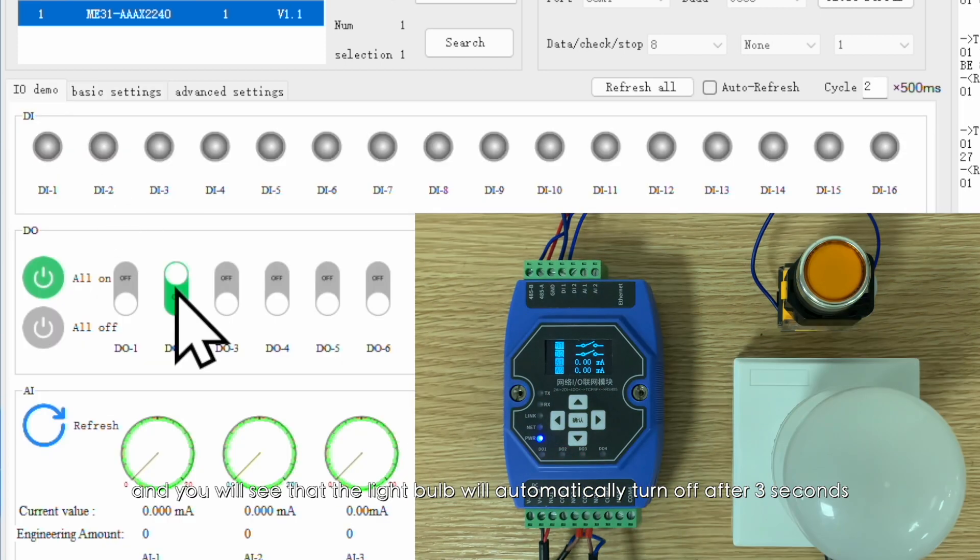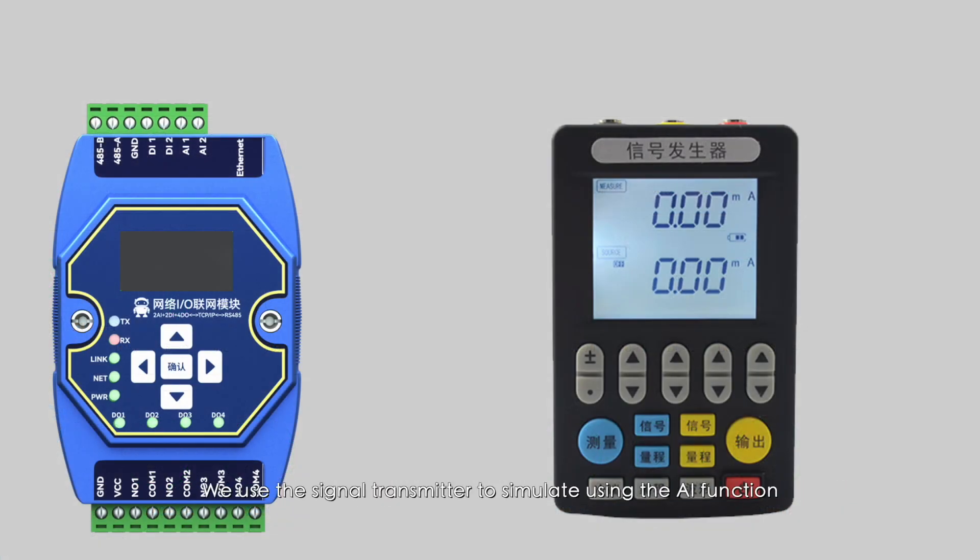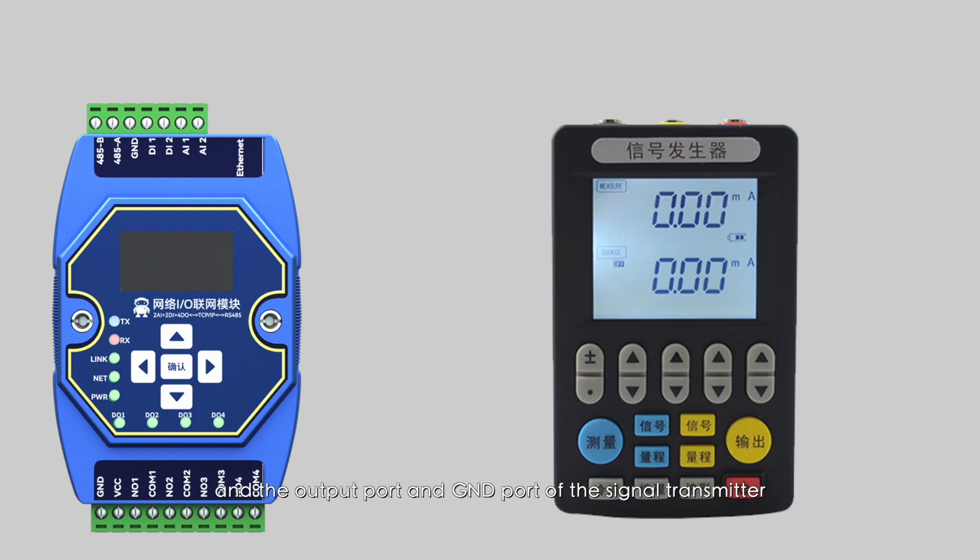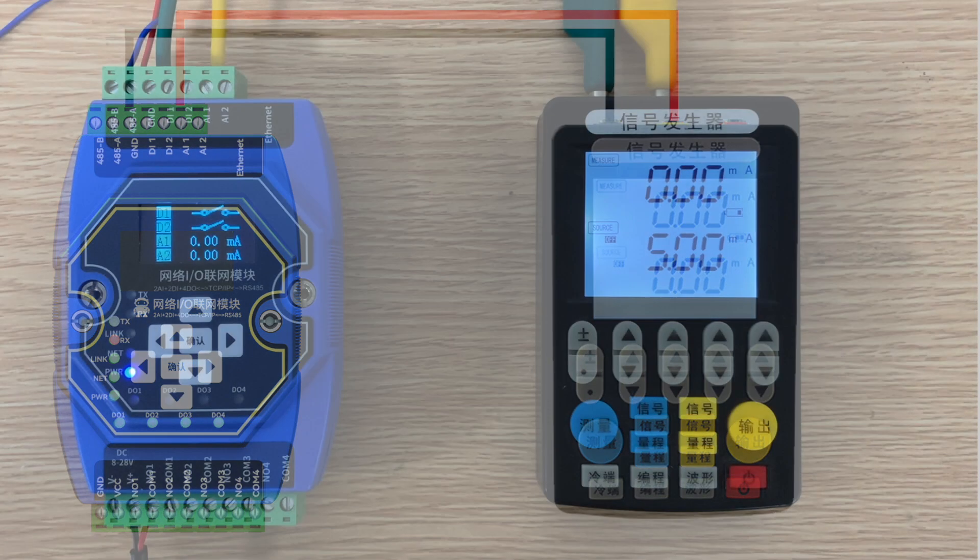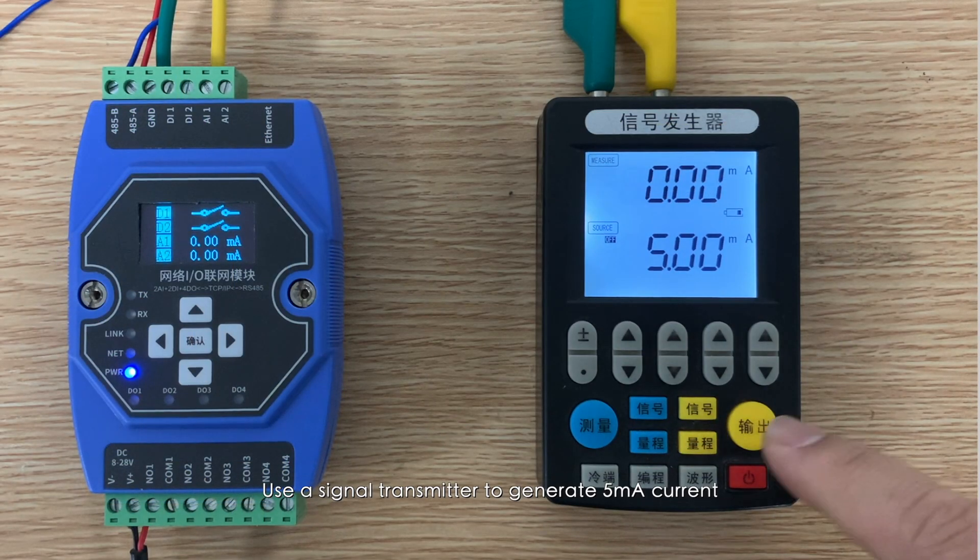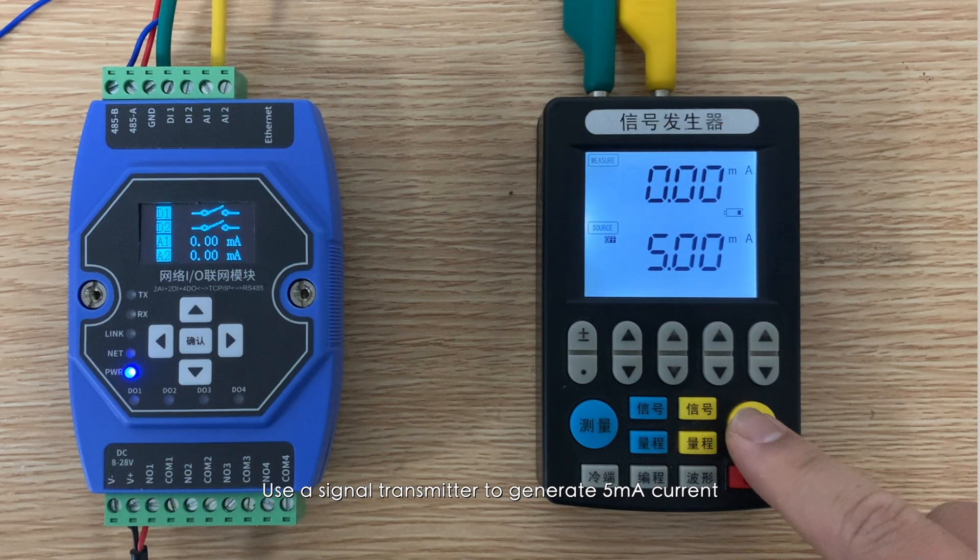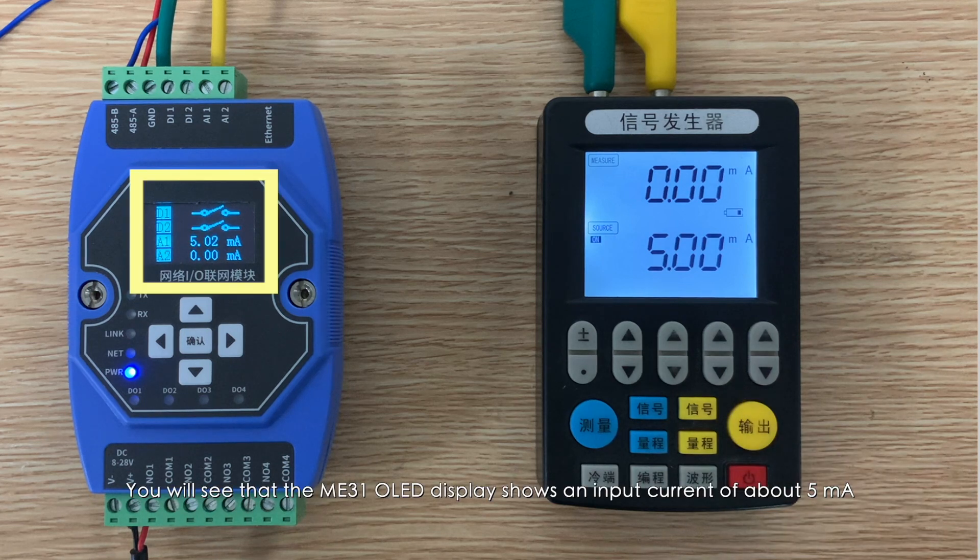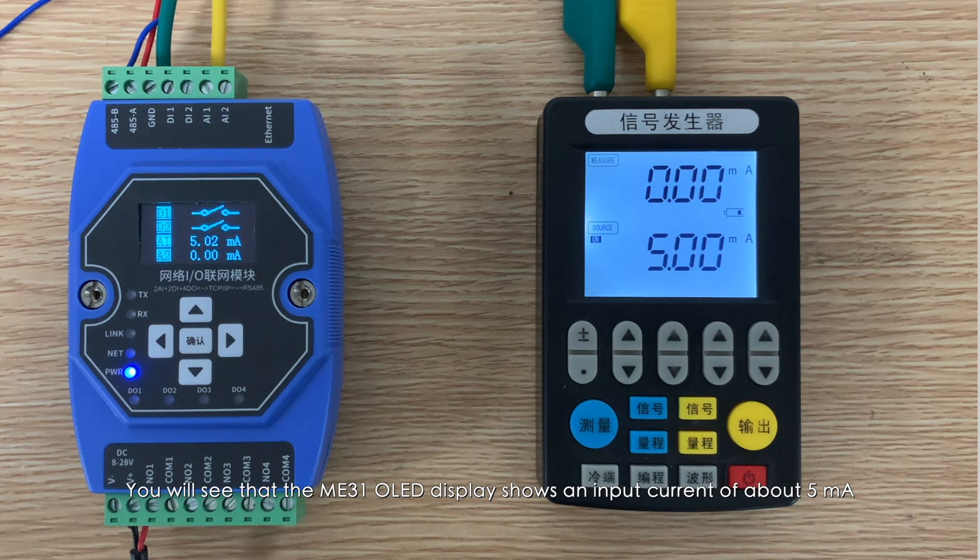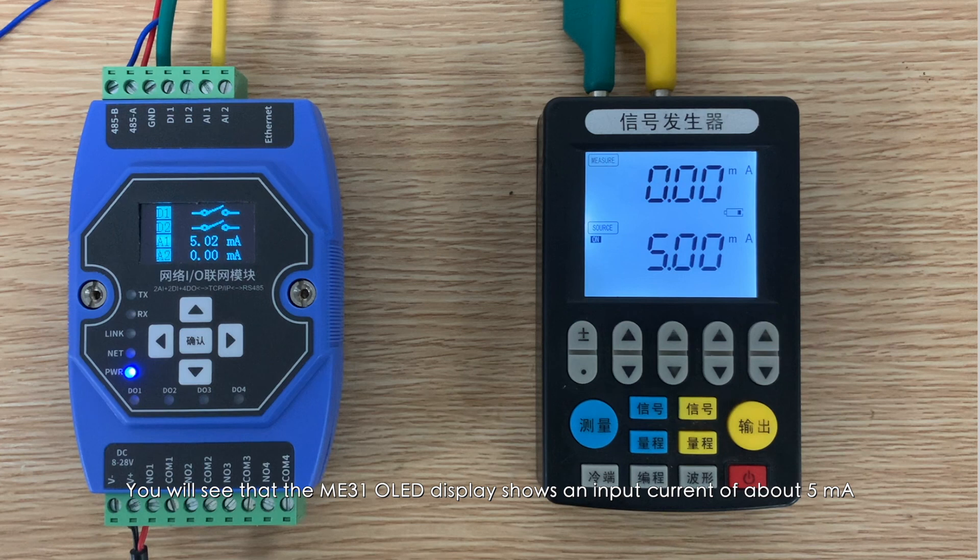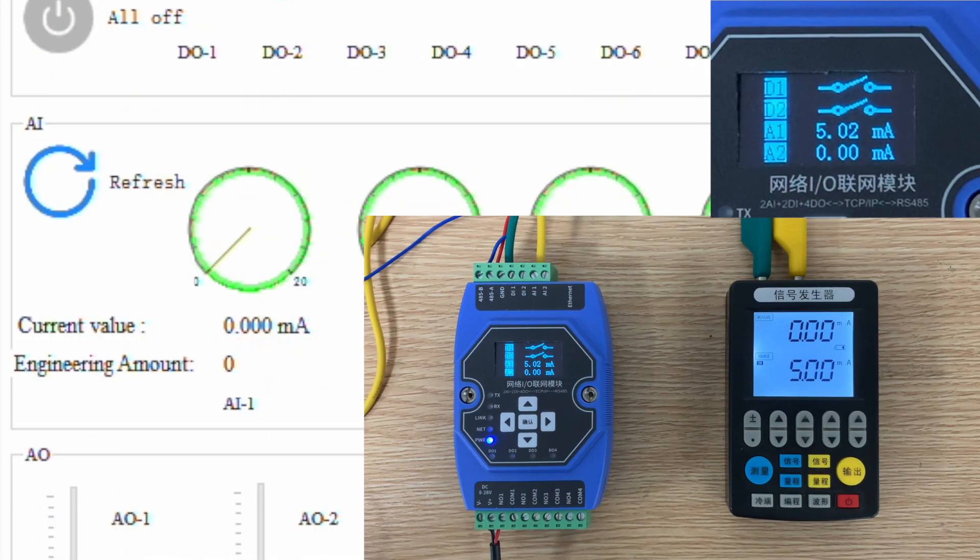We use a signal transmitter to simulate using the AI function. The output port and GND port of the signal transmitter are respectively connected to the AI1 and GND ports of ME31. Use the signal transmitter to generate 5 milliamps current. You will see that the ME31 OLED display shows an input current of about 5 milliamps. Open the configuration tool to refresh the AI, and you can see that there is also a 5 milliamps current input.